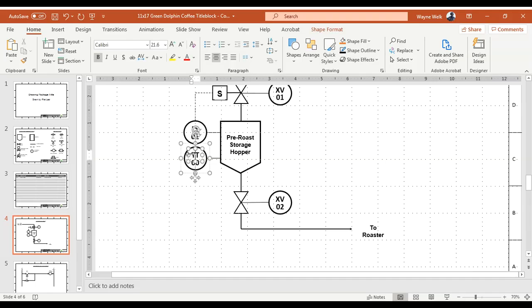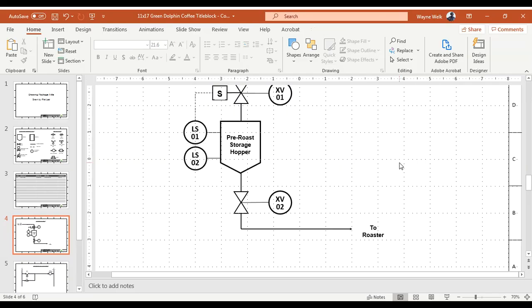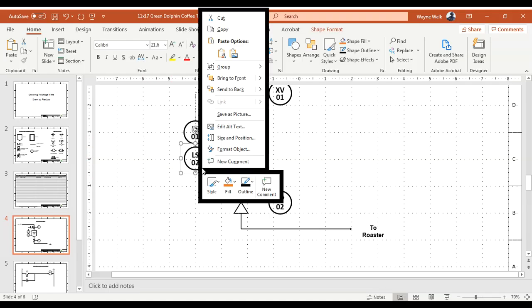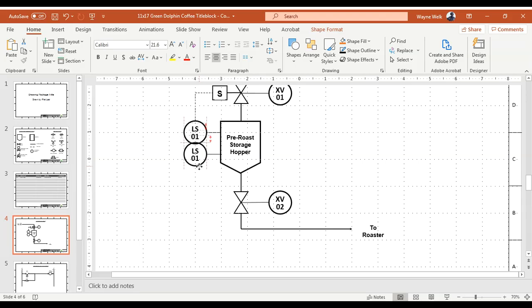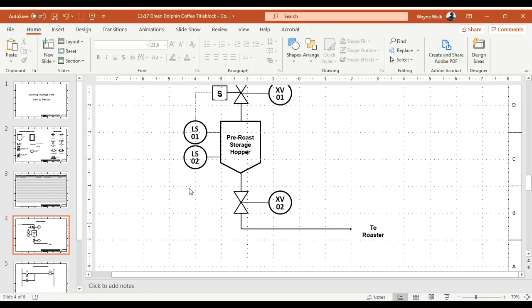In this case we'd show the solid connection, and then a dashed line going off to whatever we're controlling. We'd change the label to 'LS' — and since we already have LS01, this one would be LS02. Another option would have been to select both the instrument symbol and the line, right-click and copy, then paste — giving an exact copy that you just relabel as LS02.